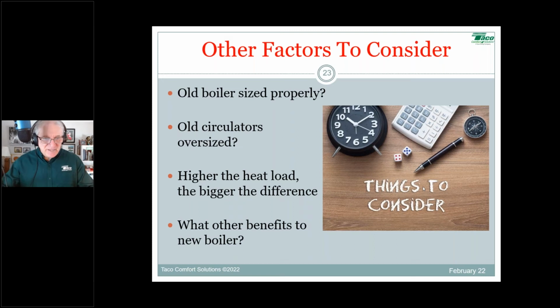If you can't change the emitters, if this is a replacement application and the emitters are the emitters and you're not doing anything different, you kind of keep it straight to straight. But outdoor reset and potentially lowering the water temperature, if you do the math right and know what the emitters do, can only help the situation. So you should factor that in, it's just a little harder to quantify numbers-wise.